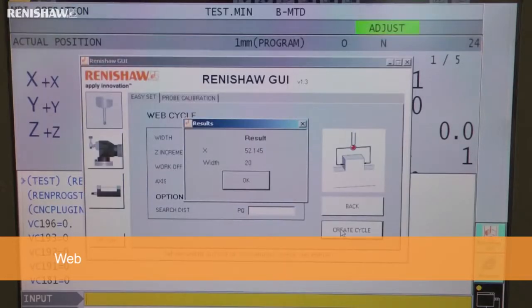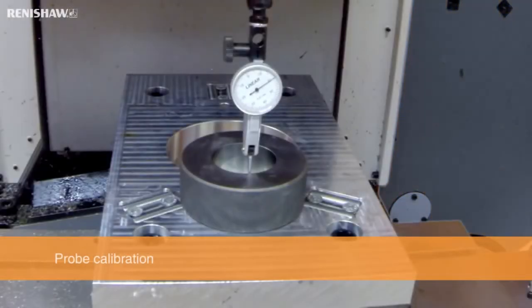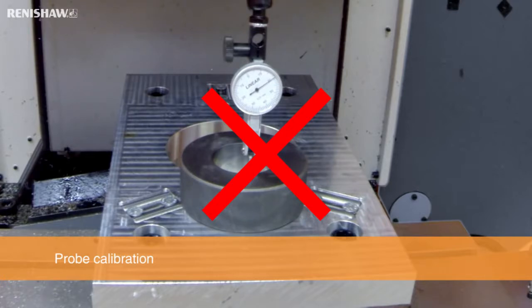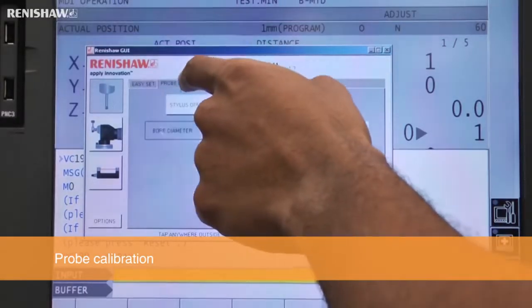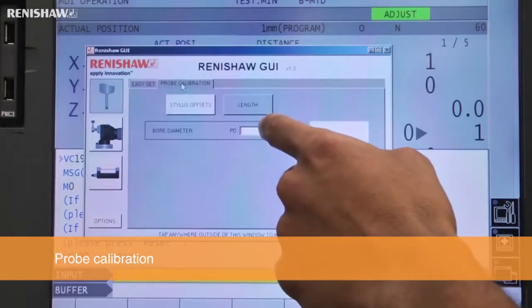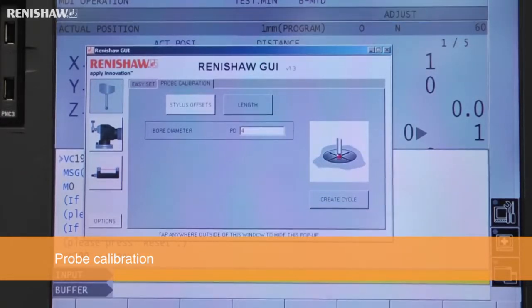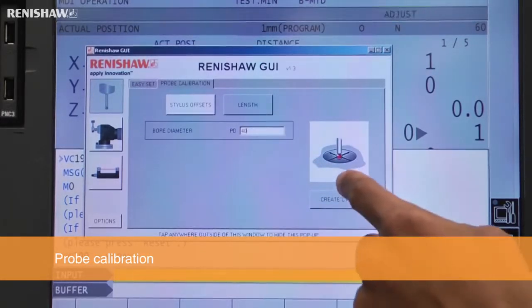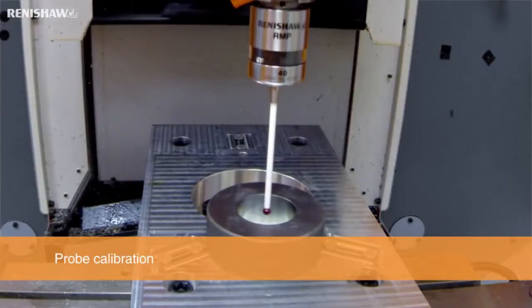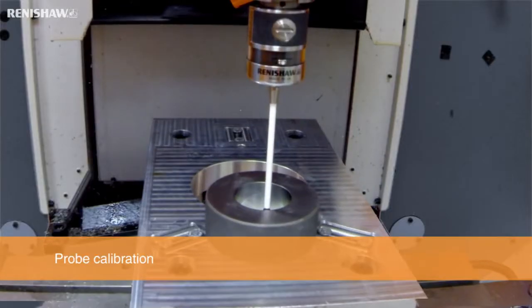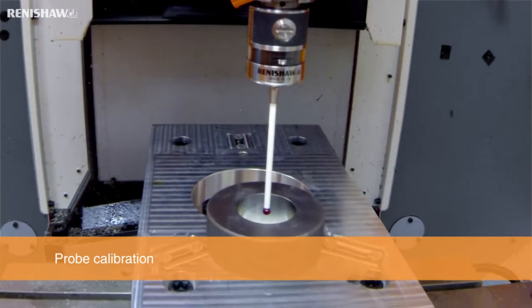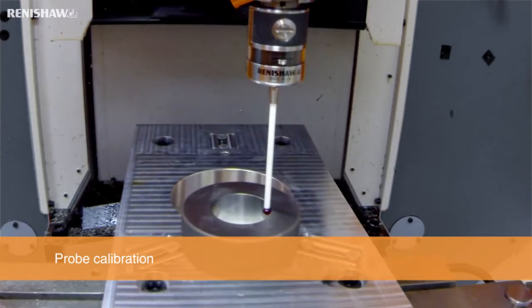The GUI also features simplified probe calibration cycles. There is no longer a need to manually establish the center of a master ring for calibration. Simply select the probe calibration cycle and enter the master ring size, then create and run the cycle. This routine will use the spindle's 0 and 180-degree orientations to find the master ring center automatically.